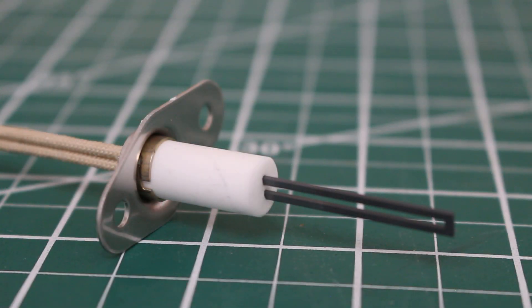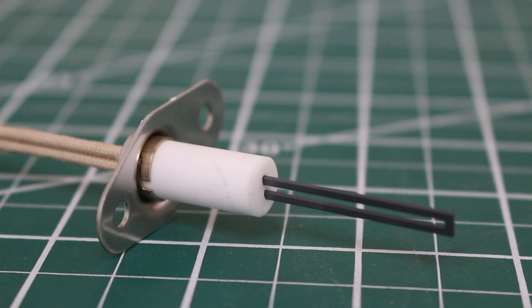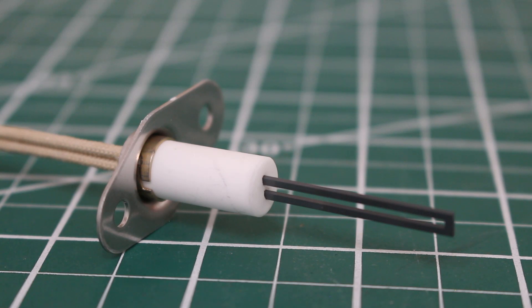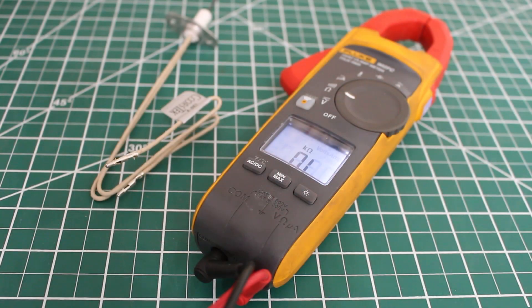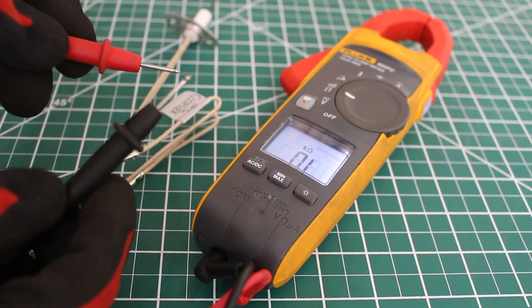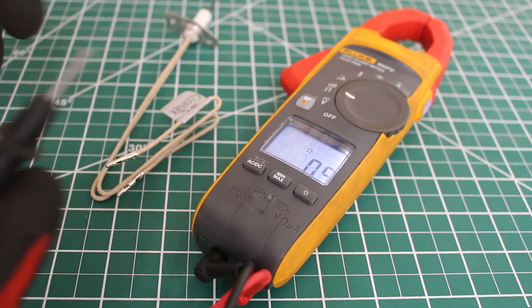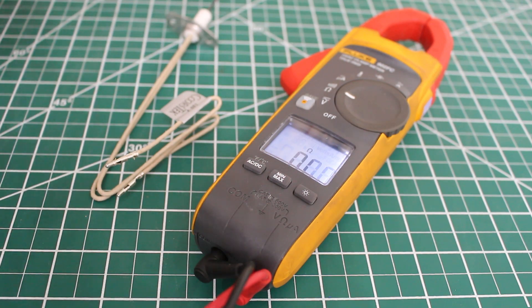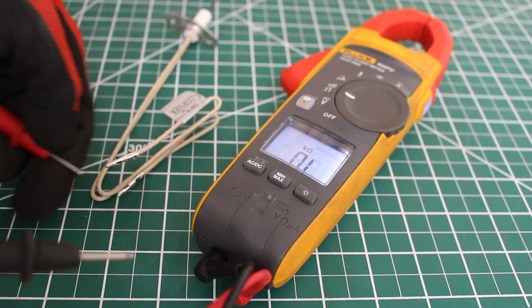Next we're going to be checking a hot surface igniter that we know is 100% good as it is brand new. If you look at the ceramic material it is not discolored and is in shape. Have the meter set to ohms and resistance. Simply going to short out the leads. We know we're good. And we're just going to check across the two wires.